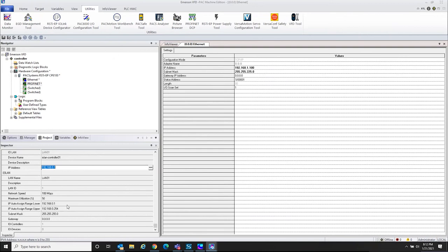This is wide open — the first slave device will be set at one. The beauty of the Profinet controller is I can have up to 10 different slave devices, and I don't need to manually set IP addresses on them. They'll automatically get assigned by names. We'll use the Profinet DCP tool to find all devices on the network, give them unique names, and if you ever have to replace a drop, just give it its name and all the parameters will be automatically downloaded over the Profinet network.